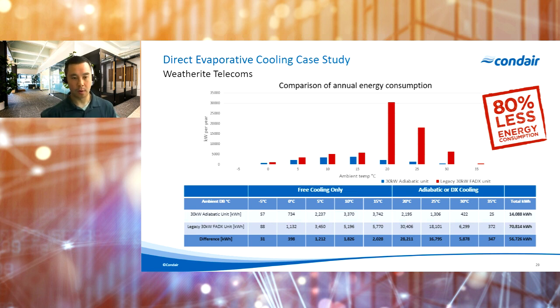You can see that for the free cooling mode only, there is a slight energy reduction on the adiabatic unit, and that's primarily because of a more efficient fan motor and fan blades, but for all intents and purposes, they are relatively close because they're both running in free cooling mode. Where we see the significant energy reduction is when we start reaching that 20-degree ambient air temperature and we have to turn on the adiabatic cooler or operate in DX cooling mode. The majority of those savings is between 20 and 30 degrees, and you can see a significant decrease in the total amount of energy needed to operate these two systems.